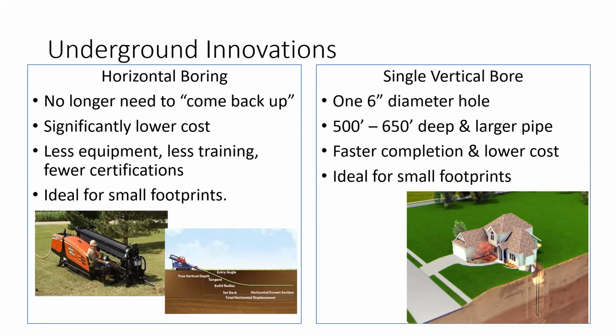We're now at the point where we can do a single vertical bore, 500 to 650 feet deep, and give 5 to 6, really 6 tons of cooling or heating. We're doing that a lot in the Rochester, Buffalo area of New York, where it gets to be 35 below zero, providing 100% of the heat with no backup heat from a single borehole. That's much cheaper, much faster, and much easier.